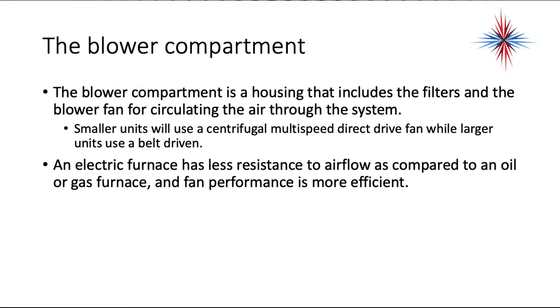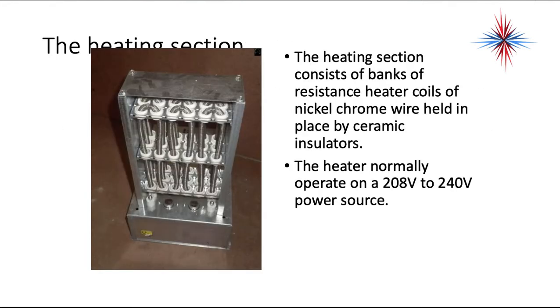The blower compartment is a housing that includes the filters and the blower fan for circulating the air through the system. Smaller units will use centrifugal multi-speed direct drive fans, while larger units are belt driven. Most residential units are direct drive. An electric furnace has less resistance to airflow as compared to an oil or gas furnace, and therefore fan performance is more efficient. The heating section consists of banks of resistive heating coils. They're made of nickel chrome wire and held in place by ceramic insulators. The heater normally operates on a 208 to 240 volt power supply.